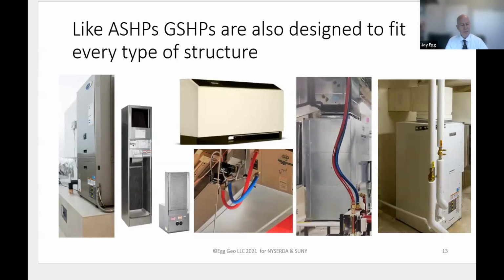The way that geothermal heat pumps can help buildings heat and cool has to do with how many hundreds of different types of heat pumps you can put into a building, whether it's a school, a university, a hospital, a hotel, or a single family home. You can choose this residential grade piece of equipment like Carrier makes, as well as all the other manufacturers here on the left. You can choose a hotel type stackable geothermal heat pump like you see here, which you might see in a Marriott or another regular hotel. This is what's called a modular heat pump, like you might see more commonly in hotels and apartments. And this is a geothermal modular unit, which these are also made in air source as well as geothermal heat pumps. You can use a horizontal heat pump that's put between floors or above the ceilings in an office or a home like you see here.